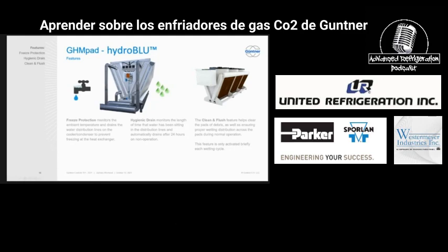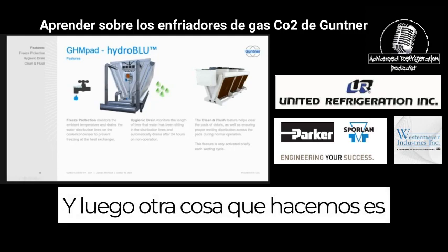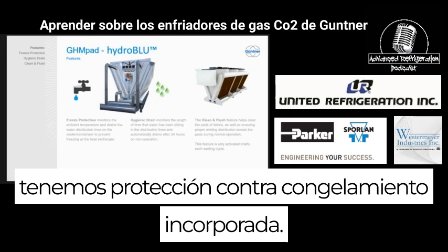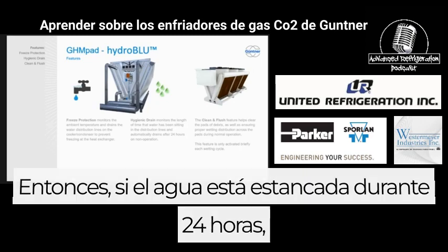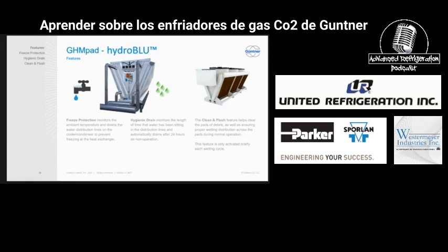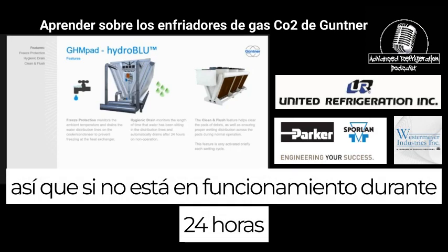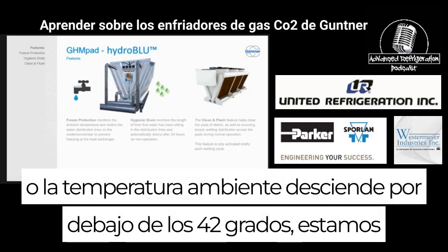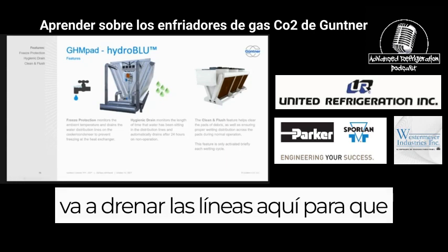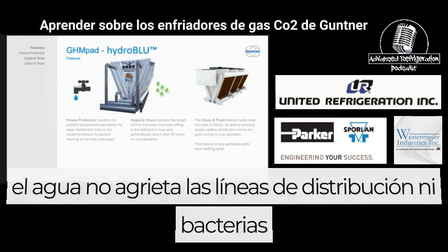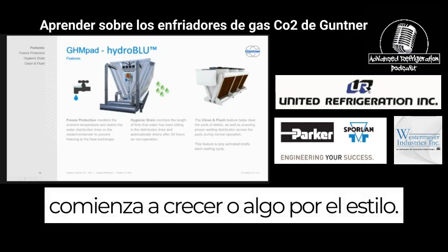Gotcha. And another thing that we do is we have freeze protection built in. So if the water is stagnant for 24 hours, if it's not in operation for 24 hours, or the ambient temperature drops below 42 degrees, we're going to drain the lines in here so that water doesn't crack the distribution lines or bacteria start to grow or anything like that.